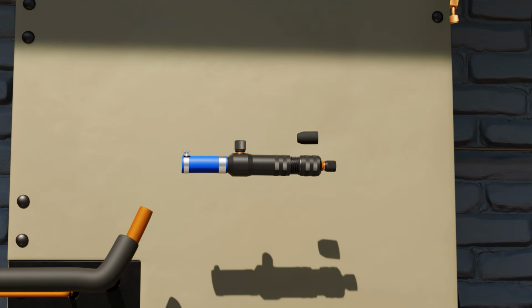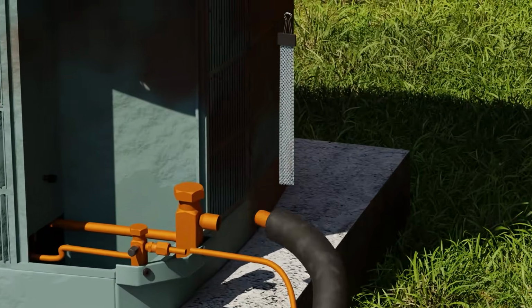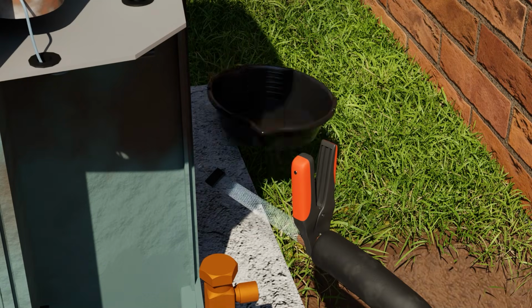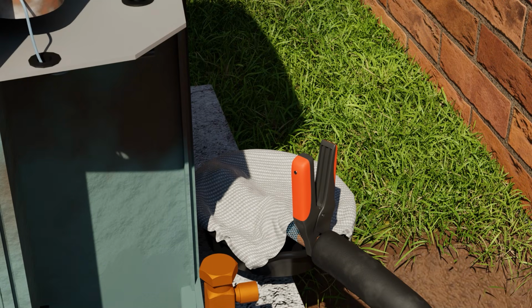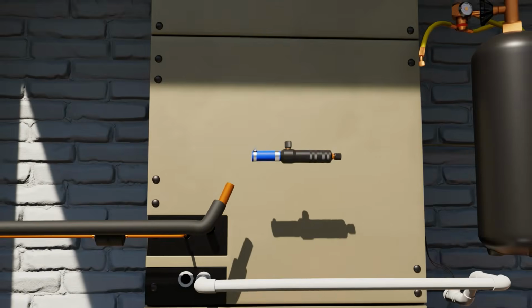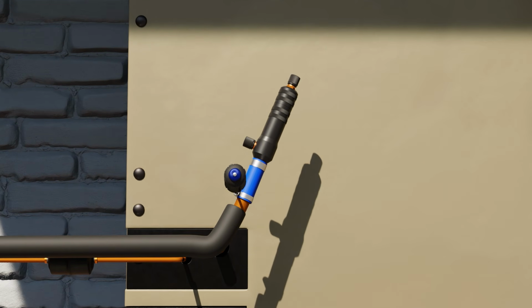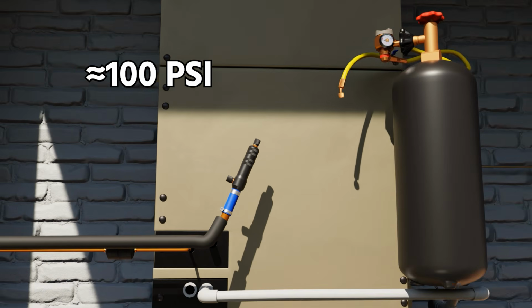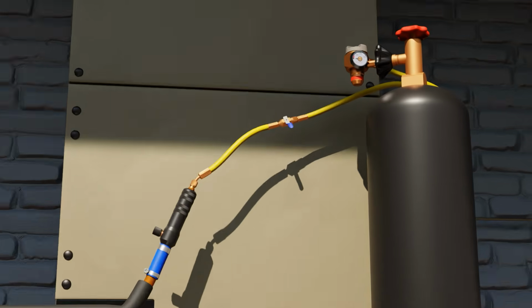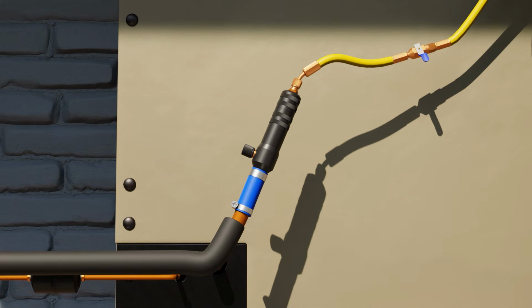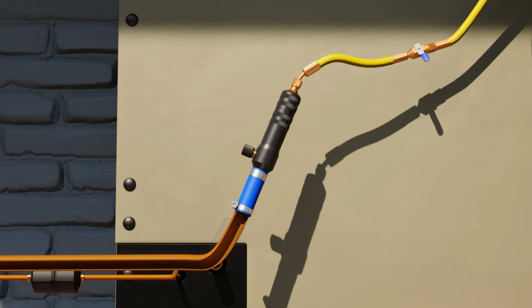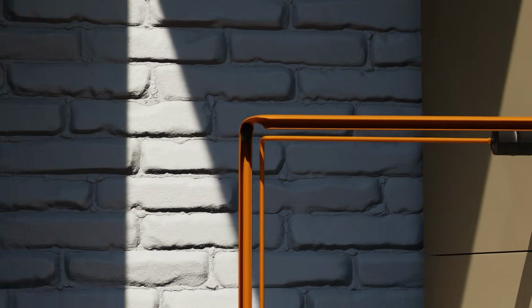Here we insert a foam pig into the pipe wiper. We put our catch at the bottom over an oil pan with a rag. This will catch any residual oil that would blow out of the system. We use a nitrogen tank and a hose, typically set to about 100 psi. We open the valve, and this forces the pig through the lines and cleans out any oil or contaminants in the lines. You'd also repeat the same process on the liquid line, which we don't show here.